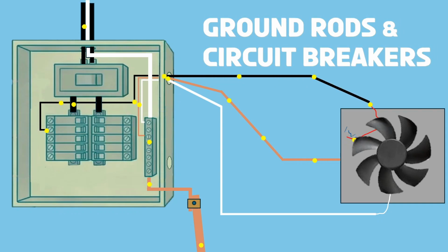A very common belief is that when an electrical fault happens in the home, the electricity goes into the ground, and that's what causes the circuit breaker to trip. That idea sounds reasonable, but it's not how electrical systems actually work. In this video, I want to show you why a ground rod will not trip a circuit breaker, and why relying on the earth to clear a fault would actually be dangerous.